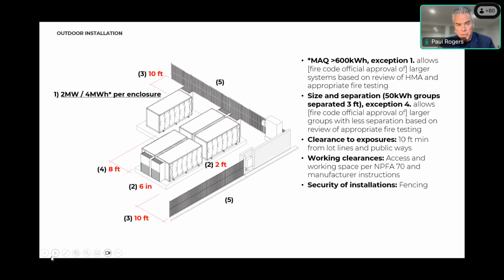The code says it's 3 feet. They tested it and said, no, we want 6 inches. They said, okay, you want 6 inches? Then make sure you prove it and do the large scale fire testing to prove that this thing will not propagate or spread to the adjoining one. And that's exactly what they did. They had 6 inches from back to back, 2 feet from side to side. And when they did that large scale fire testing, they had to set it up in the orientation in which it was going to be installed.